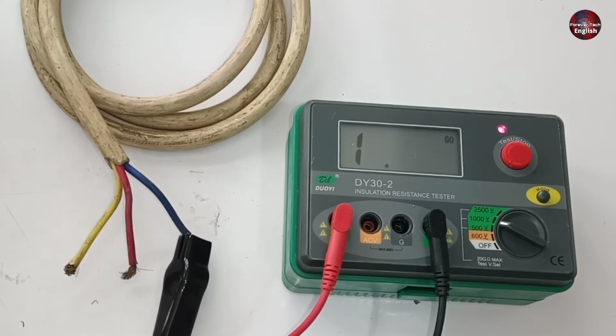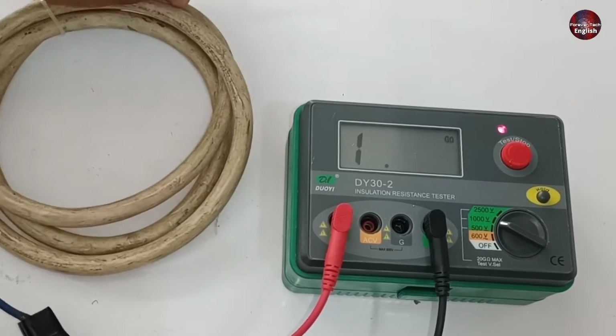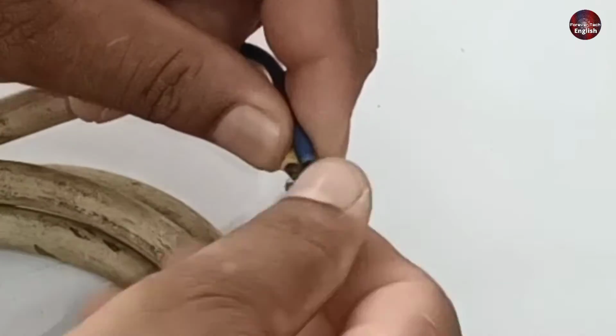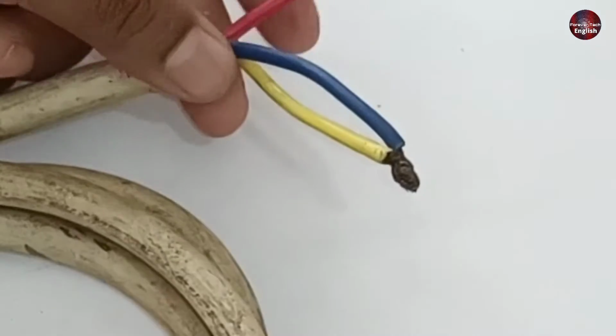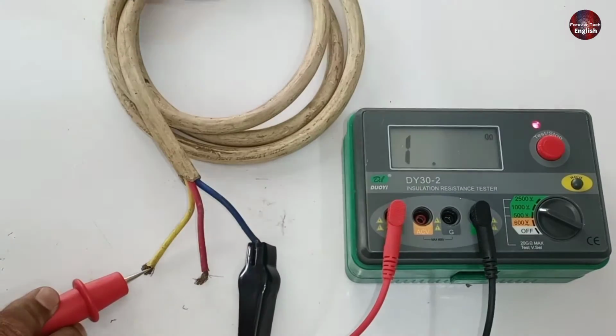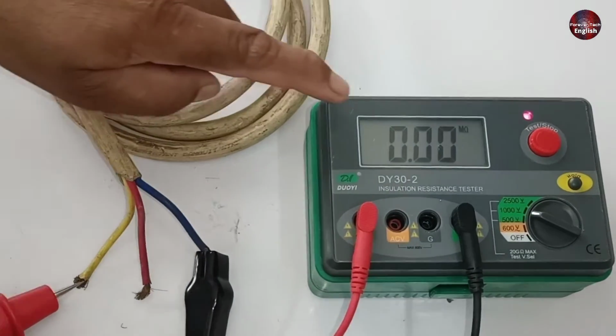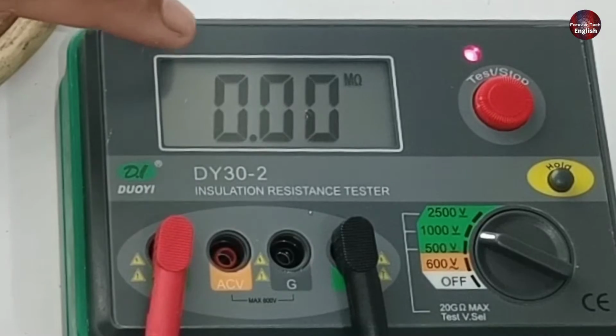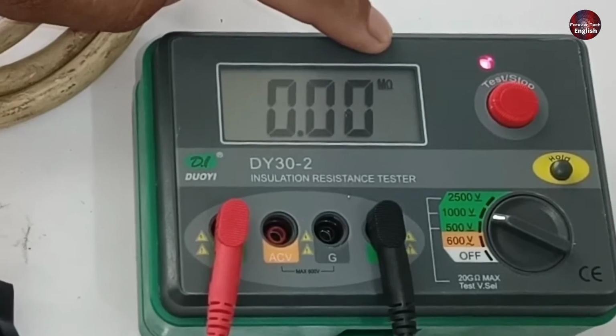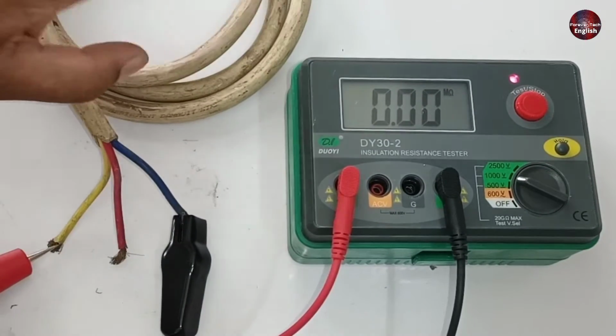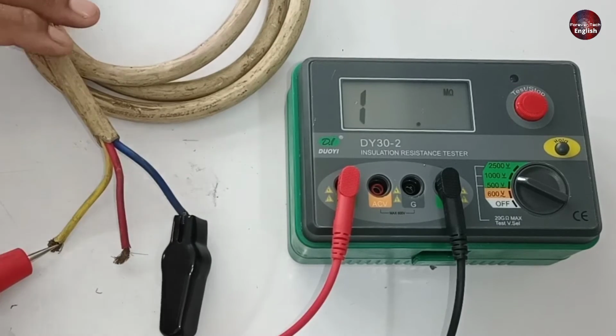For example, if the wires are short internally with each other. To show you, I have joined these 2 wires. Now I have attached the probe and pressed the test button. It is showing 0.00 mega ohms, and the tester has also started to make a beep sound, and now it has stopped displaying the value.